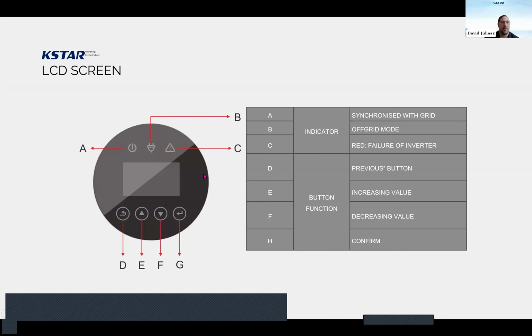About the controlling of the system, there are 3 LEDs on the top. The first shows that it is synchronized with the grid. The second shows whether it is in off-grid mode or not. And the third is red, and it shows a failure of the inverter. There are 4 buttons on the bottom of the LCD screen. First is previous, then increase, decrease value, and the confirm button.